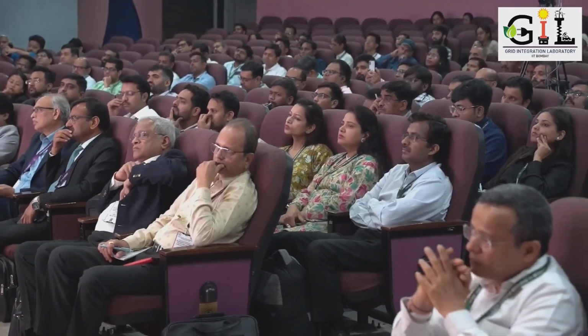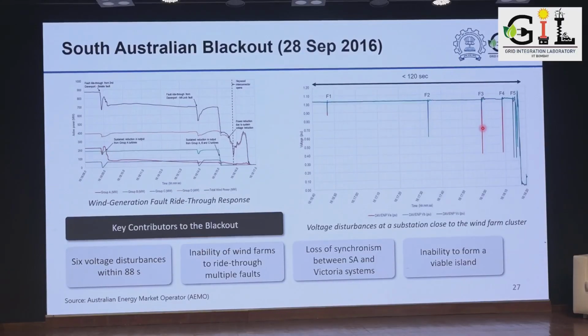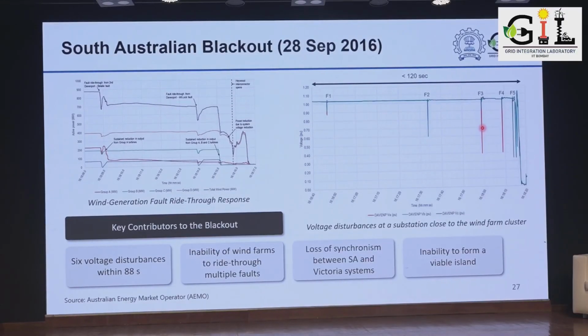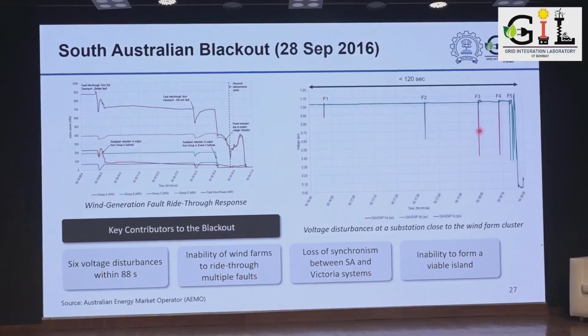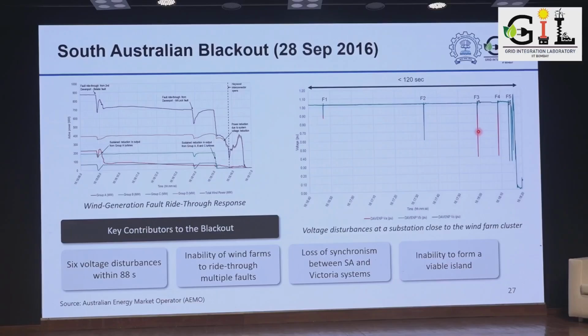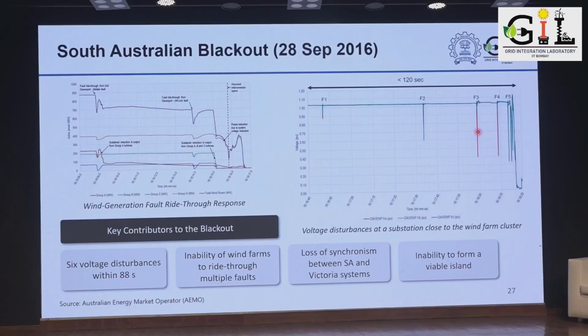There were multiple recurring faults, which, across the world, except for a few grid codes, had not been anticipated — back-to-back faults in the system. Generally, grid codes across the world talk about a single low voltage ride-through, but this event experienced several back-to-back events. As a result, the grid code was not clear about these recurring LVRTs.